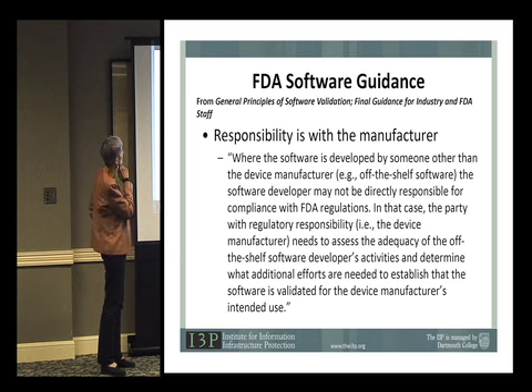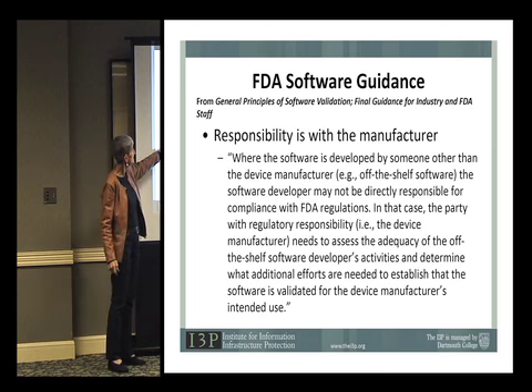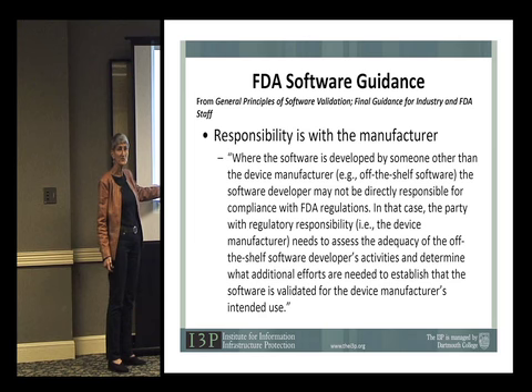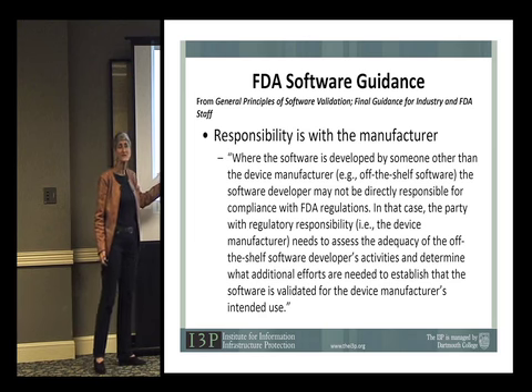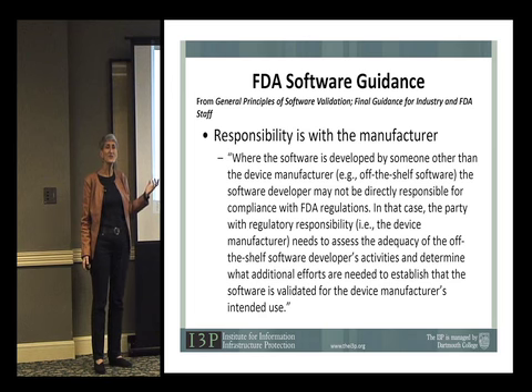Now, here are some of the guidelines from FDA software guidance. In particular, the FDA suggests that we need to assess the adequacy of off-the-shelf software in order to determine what else we need to do to validate the software for a device manufacturer's intended use. Now think about that. We're building devices now using things like commercial off-the-shelf operating systems or open source software. So how do we evaluate that? Saying that we should evaluate that is one thing. Being able to do that in some reasonable way is hard.